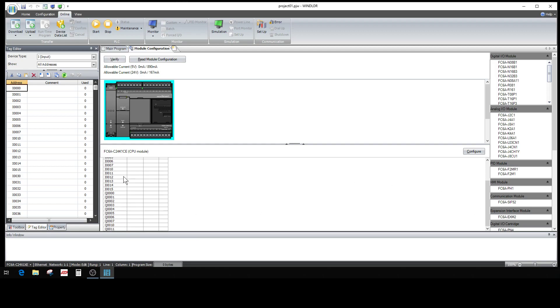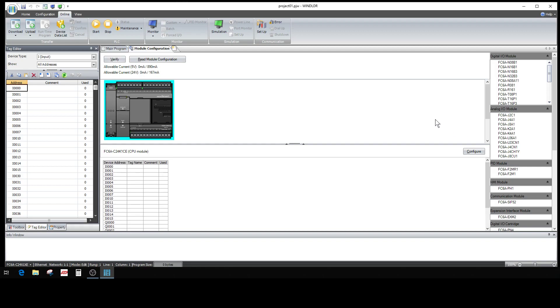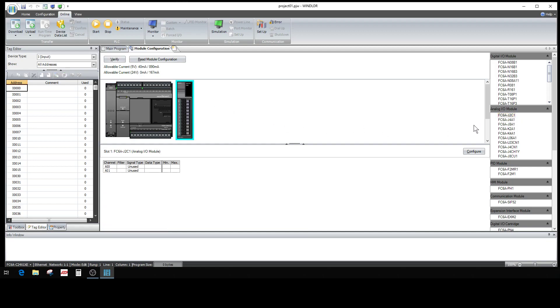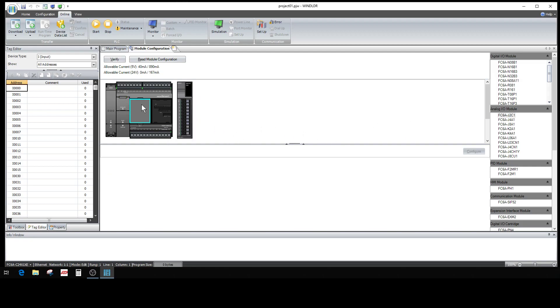The Tag Editor will fill this in for you. The scroll bar lets you move it up and down, and this will tell you what you actually have in the FC6A — how many inputs and how many outputs. I want to add some analog cards, so I'll go over here to the right menu and go to Analog Modules. In an FC6A, J2 is a two-point card — drag it right on over. That's an analog input card. I'm going to take an analog input from a field device like a temperature sensor or a flow meter that inputs a signal back to my PLC via four to twenty or zero to ten or zero to twenty milliamps. Most common that I use is four to twenty milliamp.